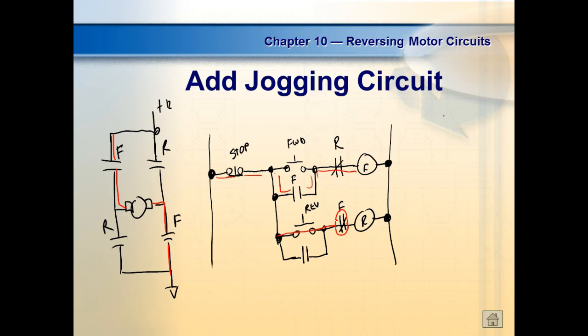So just about every reversing circuit that uses two relays, we're going to put electrical interlocks on it. And that prevents you from doing what? It doesn't prevent you from pressing the forward and reverse at the same time, and it would be impossible for you to do, but one of these guys would come in first, right? You understand? Even if none of them was running and you pressed both at the same time, whichever relay came in first, it would kick the other one out. So this is called electrical interlocks. We could also do what this guy does. Normally we like to put multiple interlocks in here in case one fails. So this is a reversing contact right here.